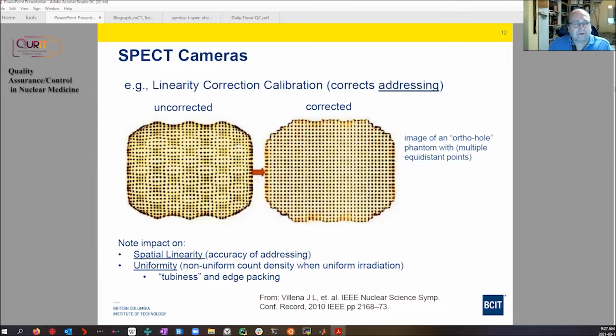On the left, you see a gamma camera detector without the linearity correction, without the corrected addresses. If you follow one line along here going down, this should be a straight line. Notice it's quite wavy. This is where the term linearity comes in. It's kind of not the best word, but it means if we irradiate a straight line pattern on the detector, it should look like a straight line on the image. But here, if we don't have the linearity correction, we get these non-linearities.